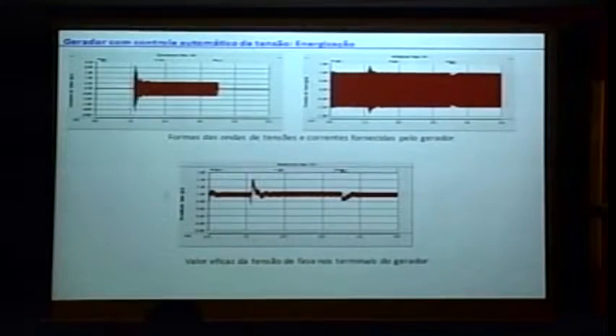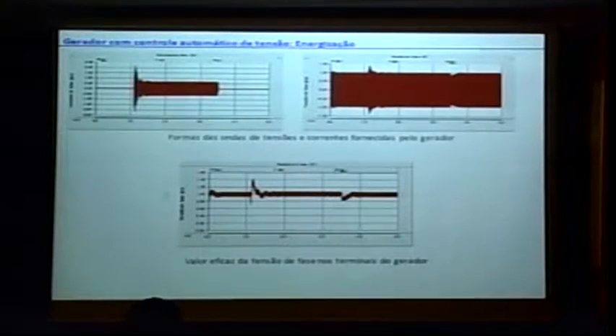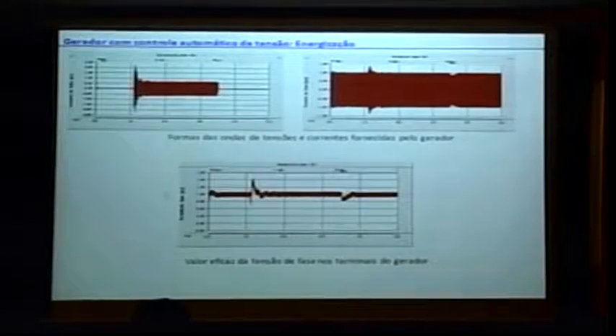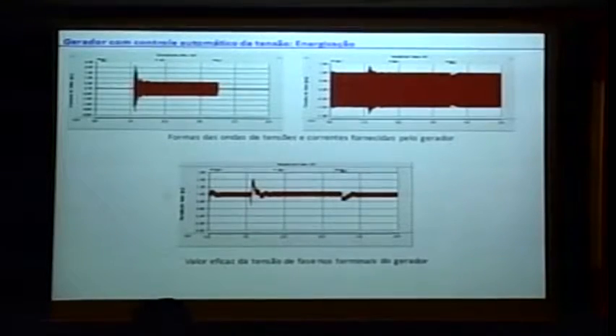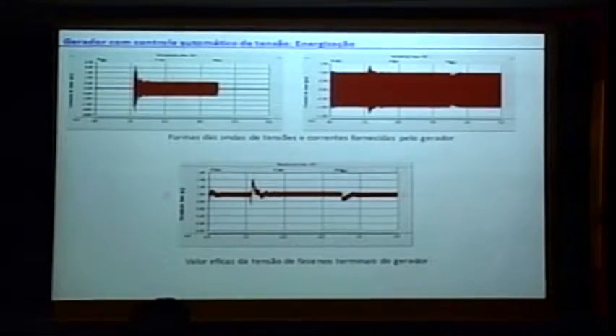Something like 100 milliseconds. Here the current drops, gets to 0.6 pu during the test till the closing of the line. So we have a transient of current here that is short-lived. The amplitude is 2 pu.